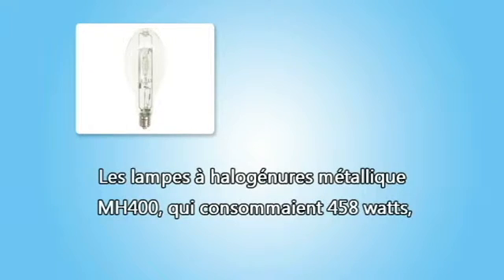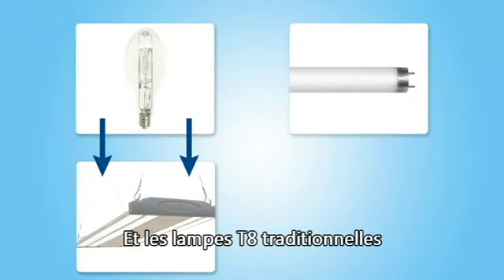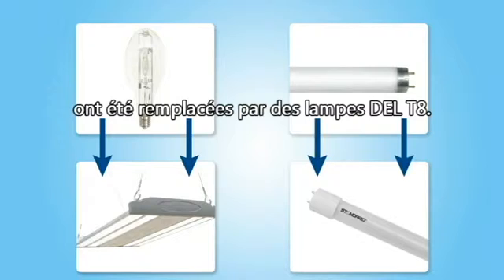The Metal Halide Lamps MH400, which consumed 458W, were replaced with 175W LED high bay luminaires. Also, the traditional 32W T8s were substituted for new 22W LED T8s.